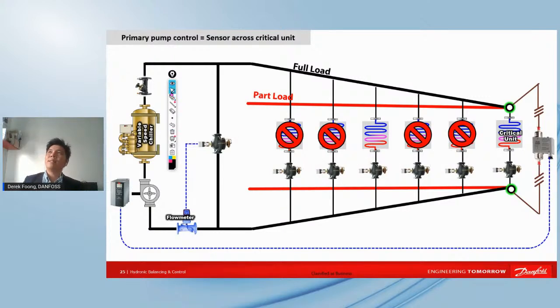In the early days, if we compare the commercial versus technical side on this part, a lot of people asked why this is twice or 3 times higher than a conventional control valve. But still today, they are using this new technology. It's very encouraging that more people are putting focus into efficiency, precise flow balancing and control.